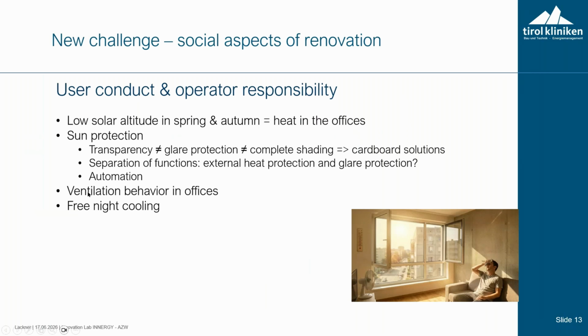Also a point is the ventilation behavior, because the users leave the offices about 4 o'clock p.m., but the sun goes down at about 8 p.m. So the sun comes through the window and overheats the room, and in the morning it's about 28 degrees, and the users say it's too hot, we can't work.